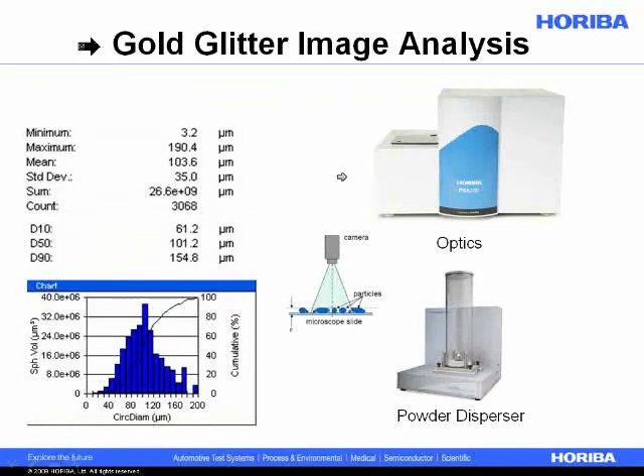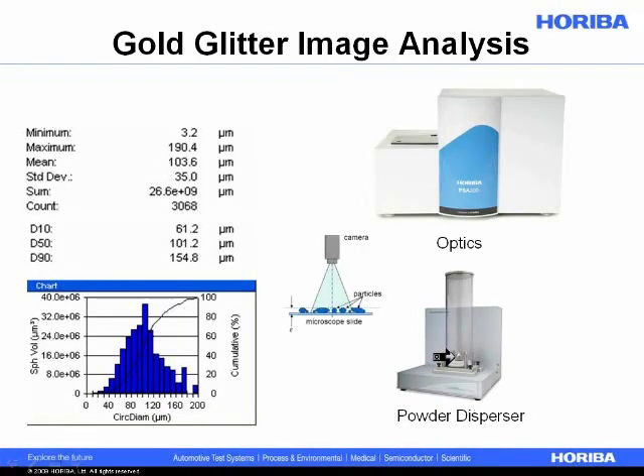That's interesting — we got similar results wet and dry. Let's use another technique to characterize this material. The next technique we use in our laboratory to support laser diffraction, or to get additional information, is image analysis. This is the PSA 300 static image analysis system, where we disperse the particles using a powder dispersor: we place the sample and slide inside a containment zone, draw a vacuum, then release the vacuum through a nozzle, and the particles fall on the slide.